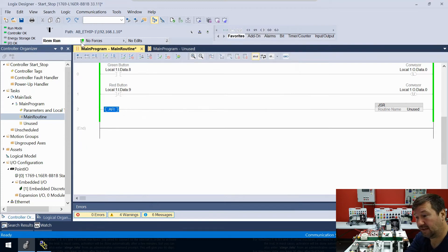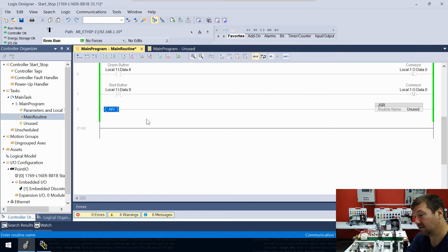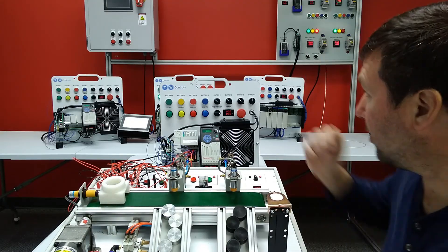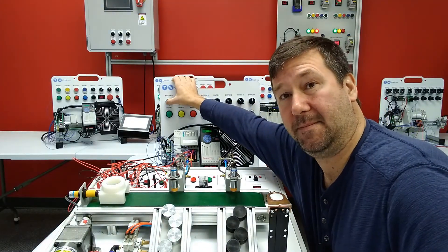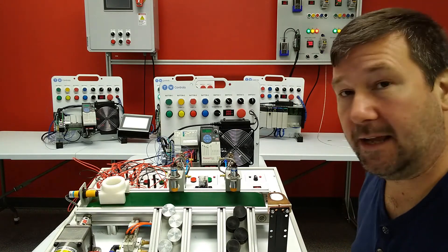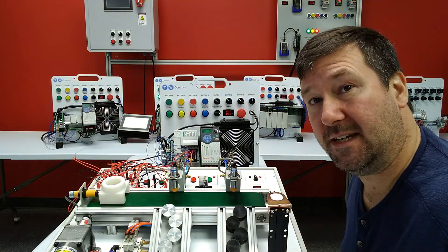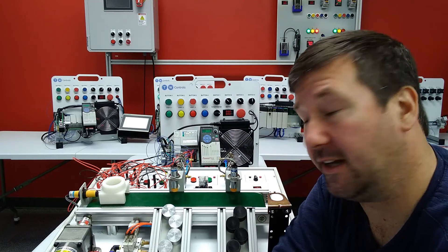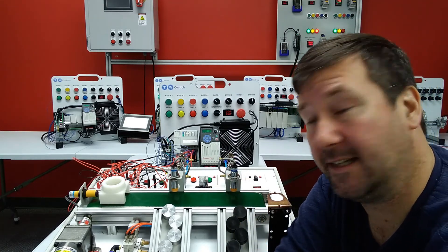Let's look at our green lines again — we have green on our main routine, but now this rung is completely disabled and there's no way that JSR can ever jump to our unused routine. But when we go to the unused routine, we do have the green line. Let's start our conveyor one more time and cycle power — our green run light is on and it is not running.